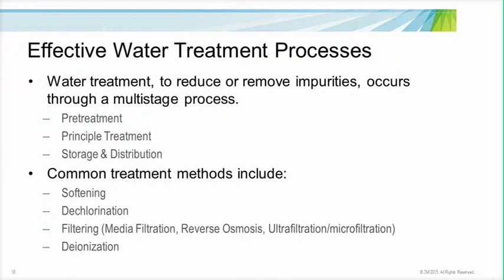Water treatment can be broken down into two main steps or stages identified as pretreatment and principal treatment. The pretreatment and principal treatment are often referred to as water quality generation. The following stages are storage and distribution of the quality water to its point of use. Pretreatment methods include softening and/or dechlorination, followed by principal treatment methods such as media filtration, reverse osmosis, and ultrafiltration or microfiltration. Deionization is typically the final treatment method prior to distribution and use.